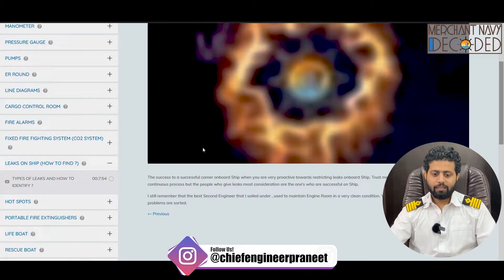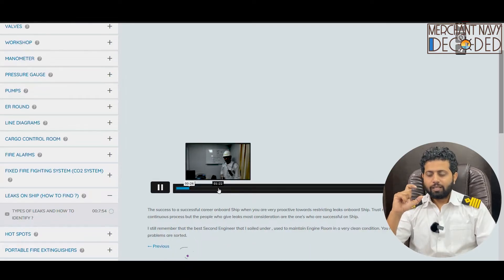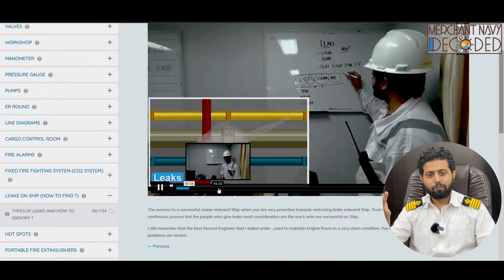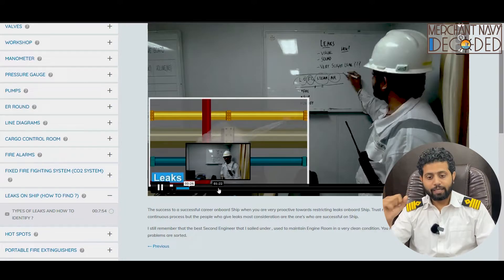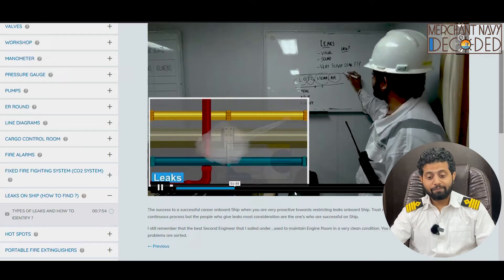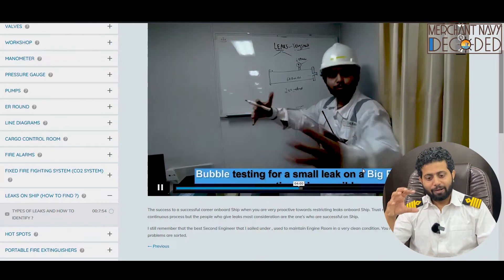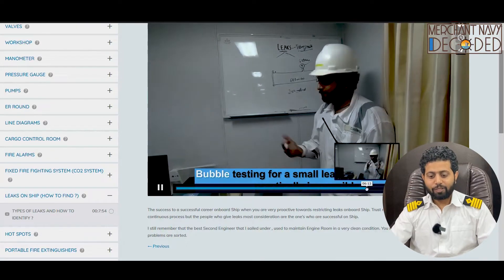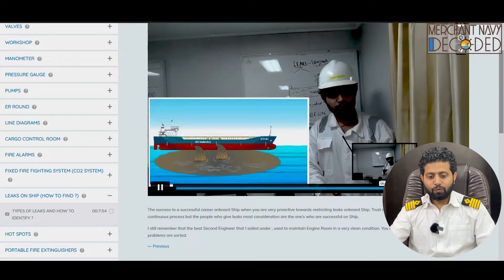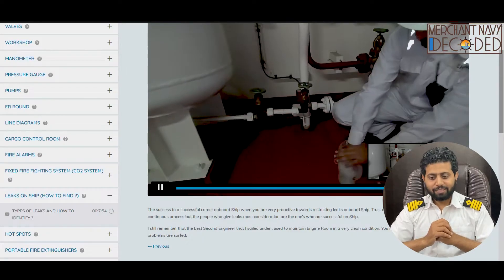Next is leaks on ship. When I talk about leaks on ship, there are a lot of types. First I'm covering the theory: leak of steam line, leak of air line, leak of fuel line, leak of lube oil line, leak of water line — how do we identify and how do we rectify. All those things covered in detail first in theory. Then I've also talked about hydraulic line pressure testing. Lastly, we are doing a bubble test — I've made a foam lather and we are going to check whether it's leaking or not. You can see — air leak.